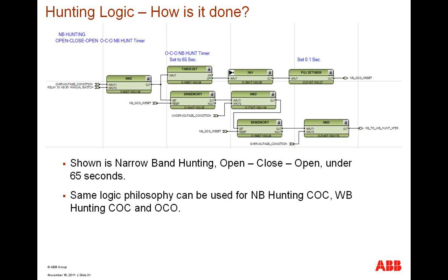So if I have an open, close, open before 65 seconds, I will drive to a narrowband to wideband transfer. I do this by a series of latch gates listed here by SR memory function block.